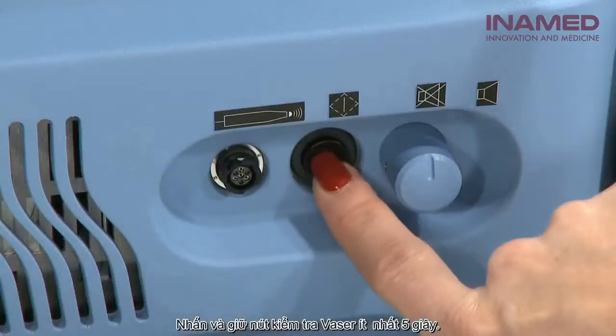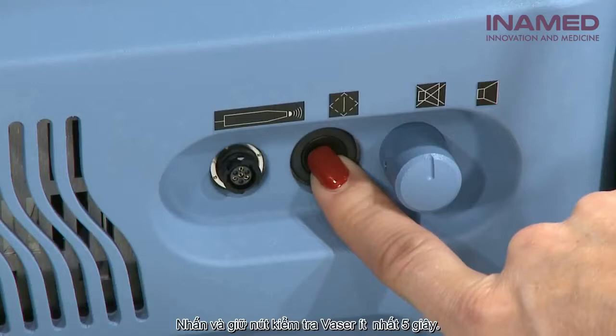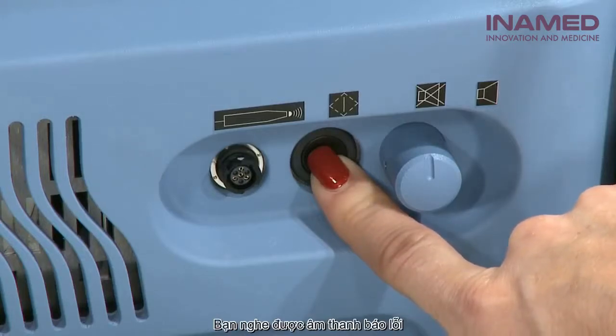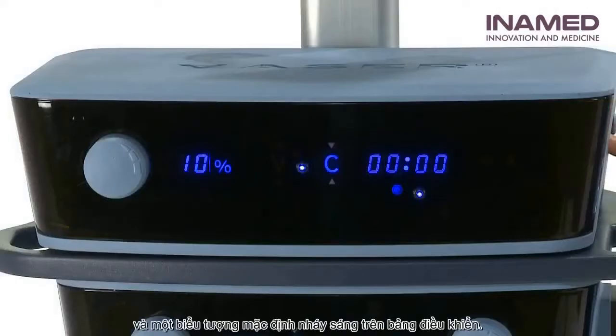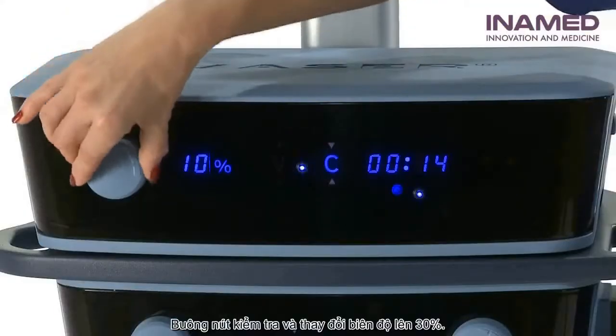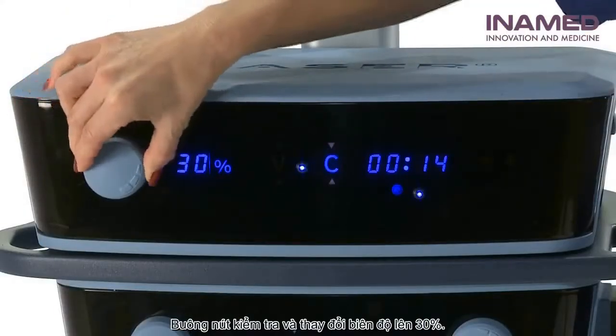Press and hold the Vaser test switch for at least 5 seconds. You should hear an intermittent beeping and see the ultrasonic wave and a fault symbol illuminate on the amplifier. Release the Vaser test switch and change the amplitude control to 30%.